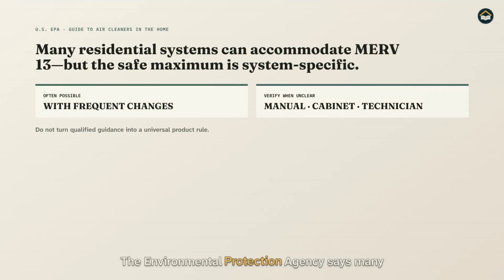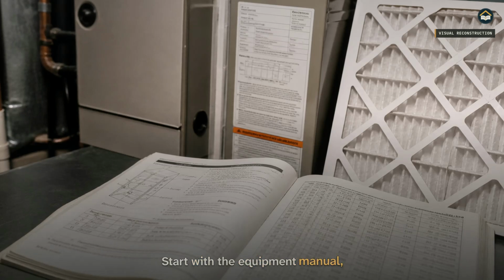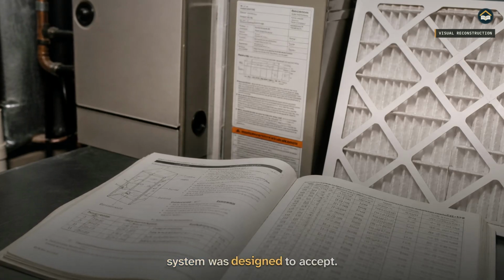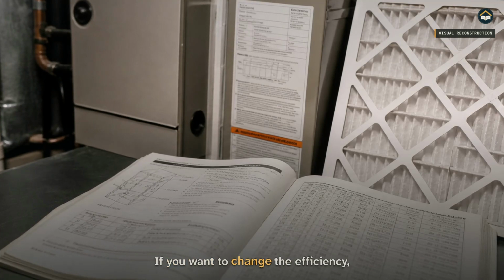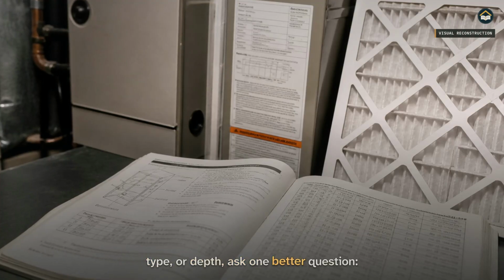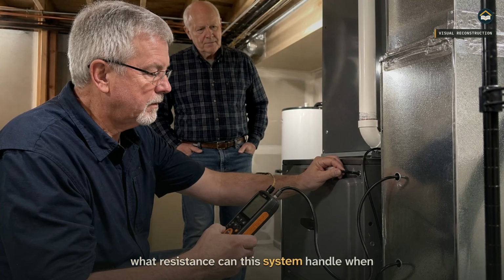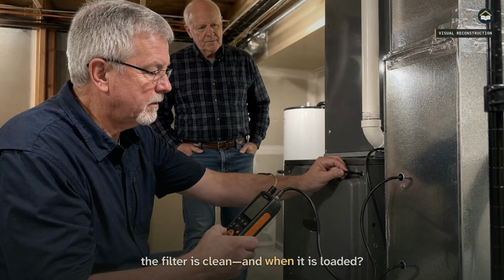The Environmental Protection Agency says many residential systems can accommodate MERV 13 when the filter is changed frequently. It also says the safe maximum is system-specific, and a technician may need to confirm it. So do not shop by fear, price, or one number alone. Start with the equipment manual, the cabinet label, and the filter the system was designed to accept. If you want to change the efficiency, type, or depth, ask one better question. What resistance can this system handle when the filter is clean and when it is loaded?